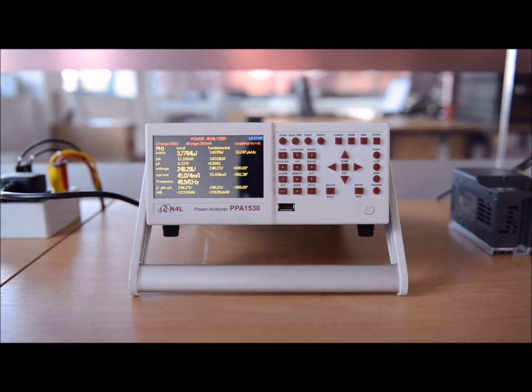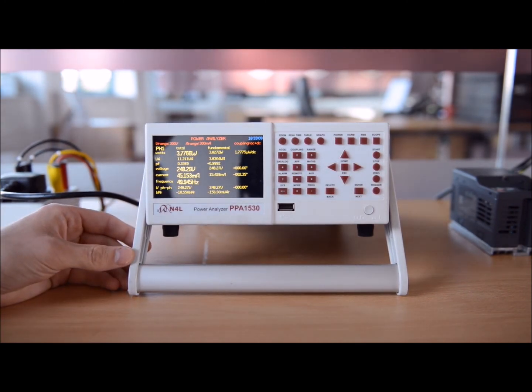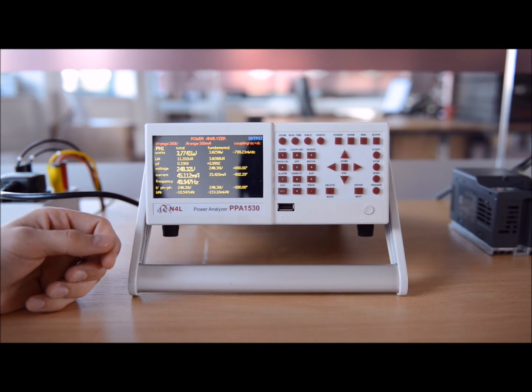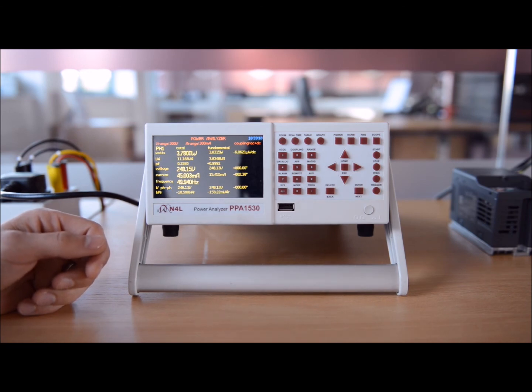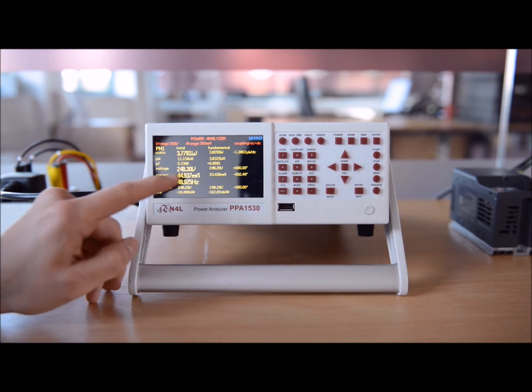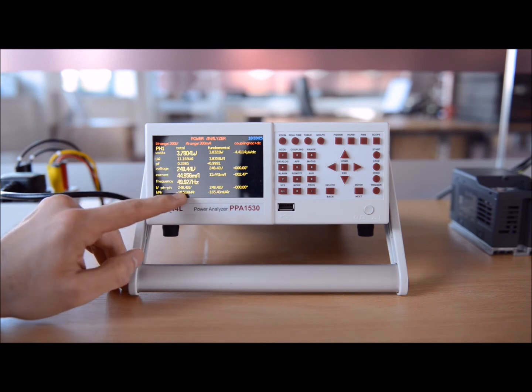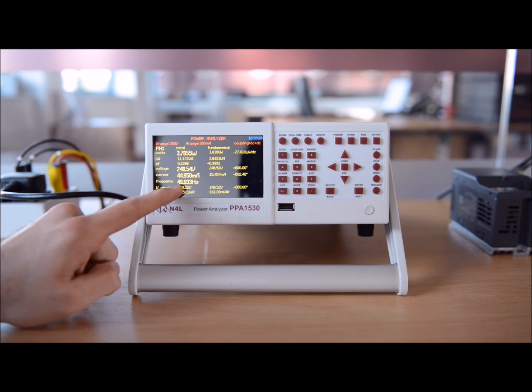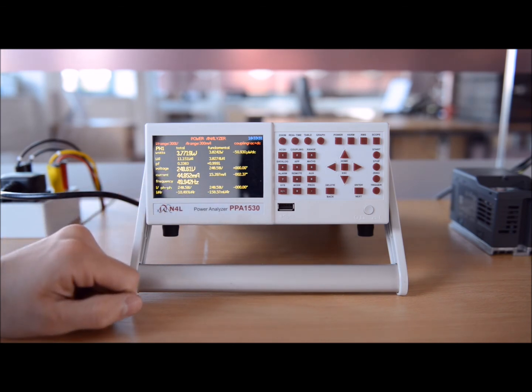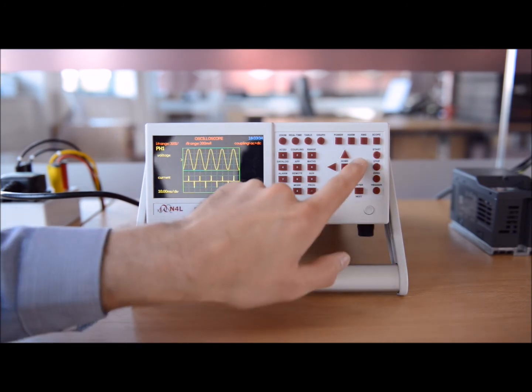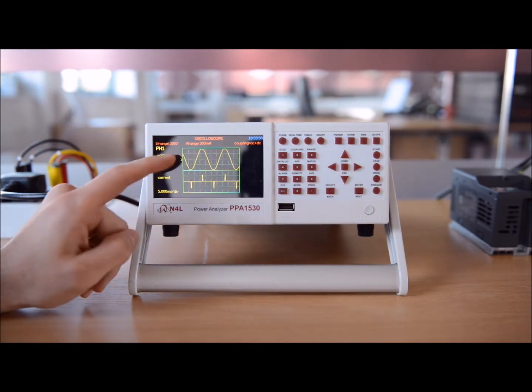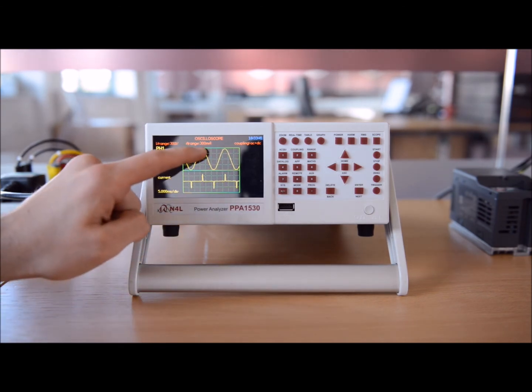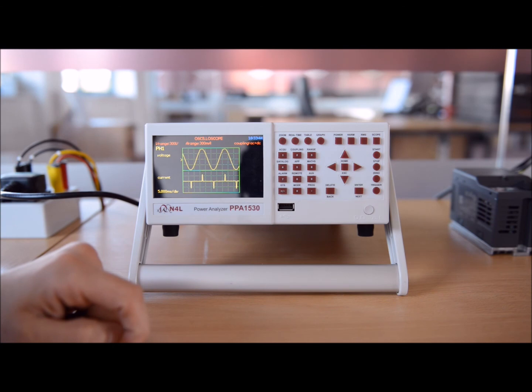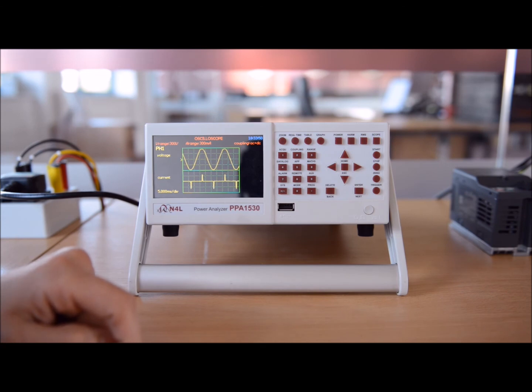So basically what we have here is the input voltage and current measurement, and of course power measurement, of the AC drive. Now the AC drive is currently in standby mode, connected to the mains, but the output's off. What we're measuring here is, as you can see, the voltage of 248.3 volts. That's UK mains voltage, approximately 50 Hertz and 44 or so milliamps. You can also have a quick look on the scope at the voltage and how peaky the current is. So typical sinusoidal voltage, slightly flat top, typical of mains throughout the world, and a very peaky non-PFC current waveform.